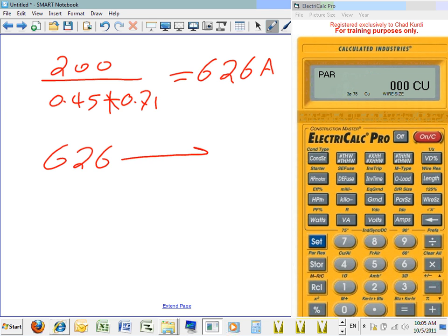626 amps. Don't ask me to parallel again here, please. Based on 310.15(B)(16) under the 90-degree column, what's the conductor that can carry this amps under the 90-degree column? Remember, we're derating. We size based on 90 now because we're derating. And copper, because Chad is vested in the copper companies.